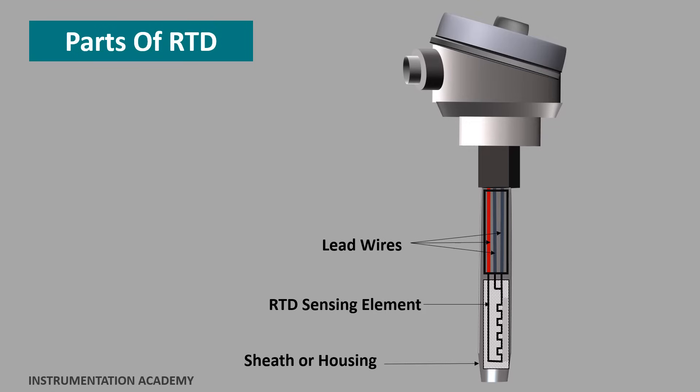Sensor sheath. The sensor sheath is constructed of metal and holds most of the component parts of the temperature sensor. The sensor packing, typically magnesium oxide, surrounds the sensing element and is contained within the sensor sheath. The sensor packing decreases the impact of process vibration on the sensing element and thus ensures a more accurate measurement.